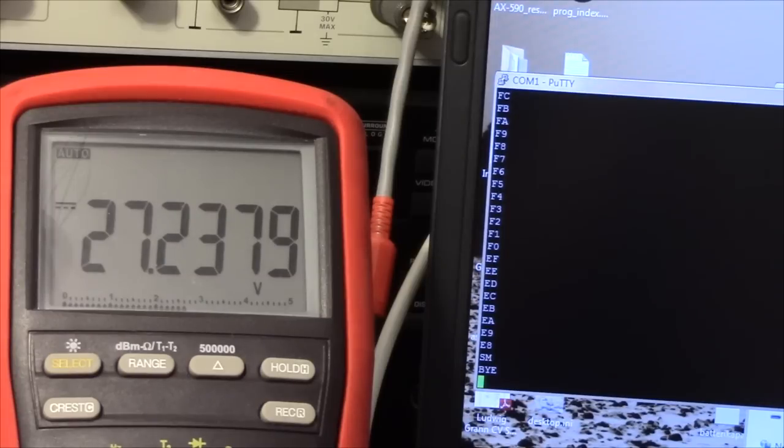And you need to do another Y after you've done that in order to put it back into smart mode, else it'll just be a dumb signalling UPS, which won't tell you your battery level or anything like that, unless your management software does a Y when you open the link with it. And that's it as far as calibrating the battery voltage of one of these things goes.